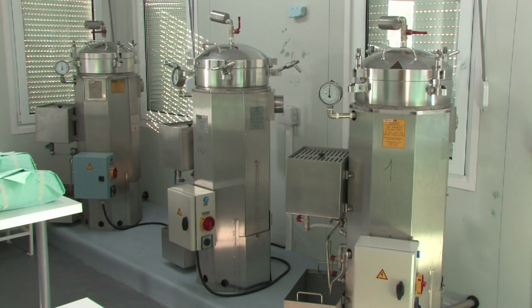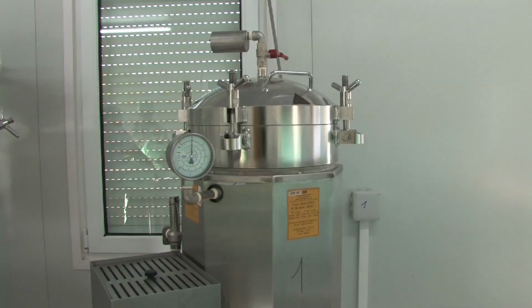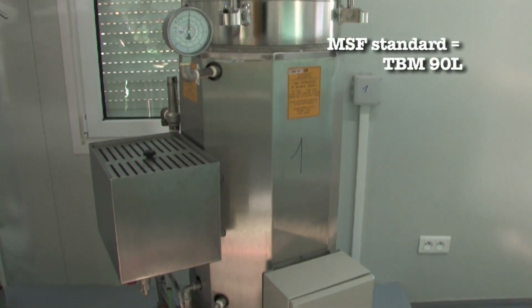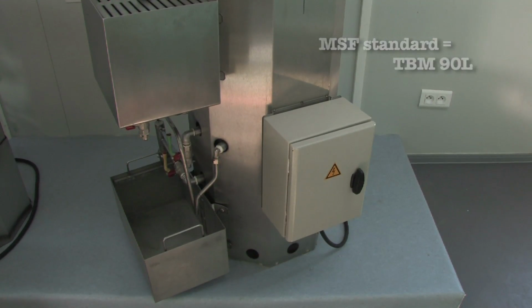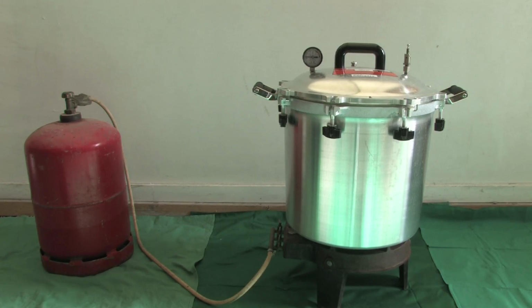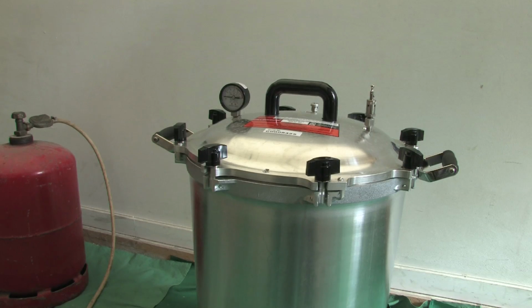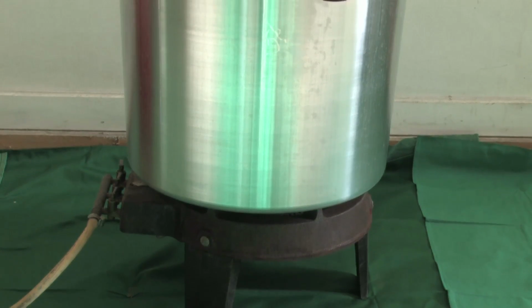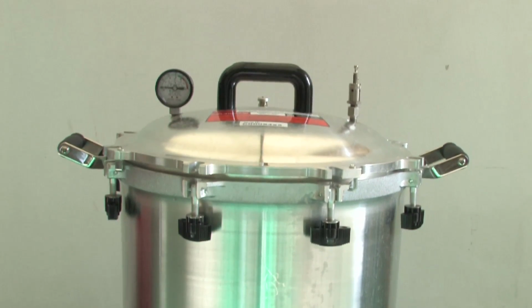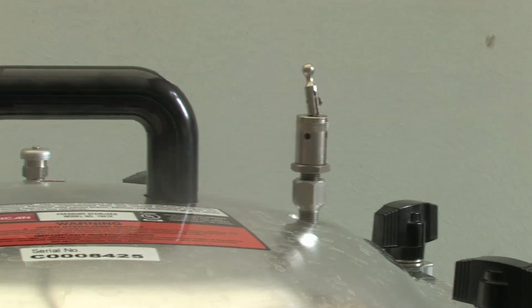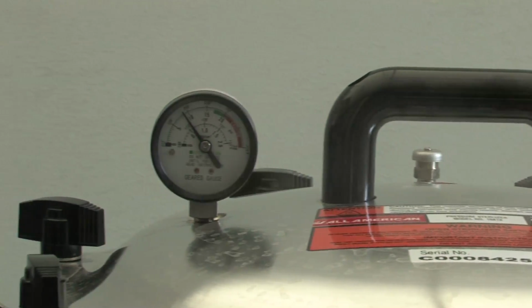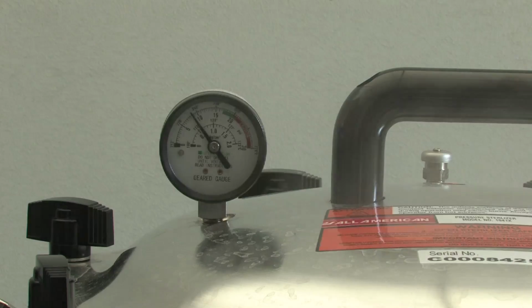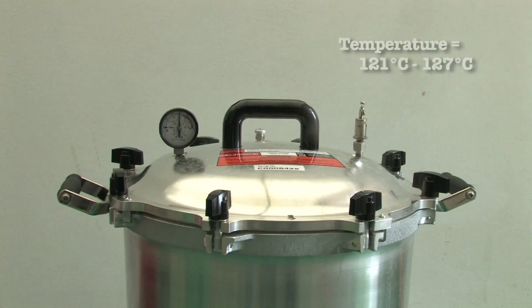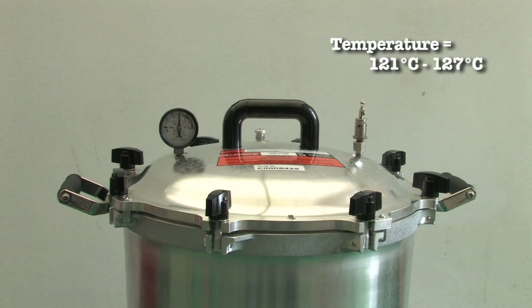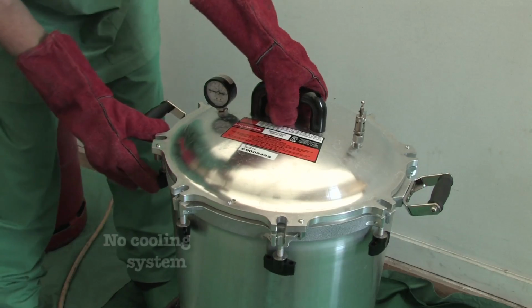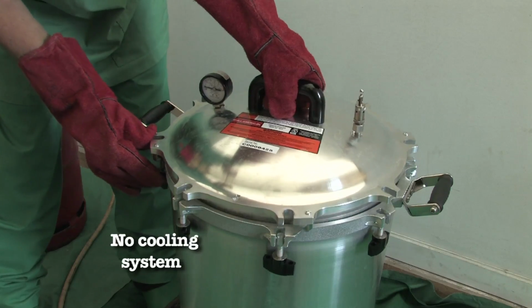The TBM 90 litre is the standard autoclave for all Médecins Sans Frontières surgical missions. However, if the TBM 90 litre is not available or has not yet been installed, some projects will use the less effective All-American autoclave. With this autoclave, 134 degrees Celsius sterilization of surgical instruments is not possible. For safety reasons, the pressure should not exceed 1.4 bars, relative pressure, which corresponds to a saturated steam temperature of 127 degrees Celsius. In addition, the All-American does not have a cooling system.